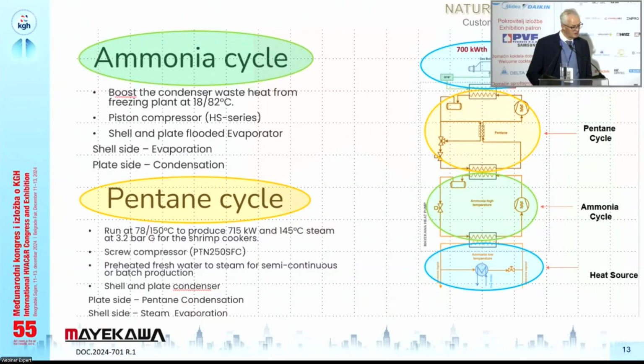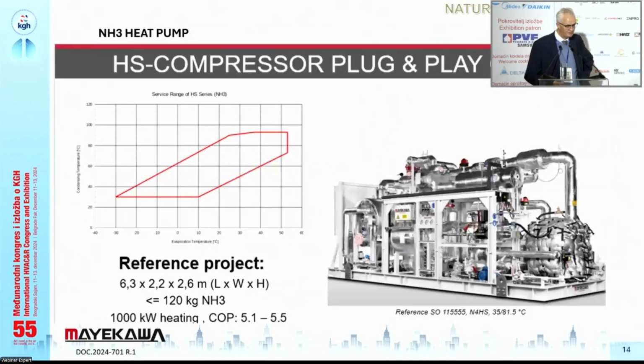So, in fact, we can summarize what you see here in the table. The energy saving obtained with this concept is 1,043 megawatt hours per year. And the expected CO2 reduction or savings is 621 tons per year. We have, with this cascade system, a much higher temperature lift because we come from 18 degrees to 140, 145 degrees, so 130 degrees lift. And we have the high temperature operation, which is very attractive for process industries.